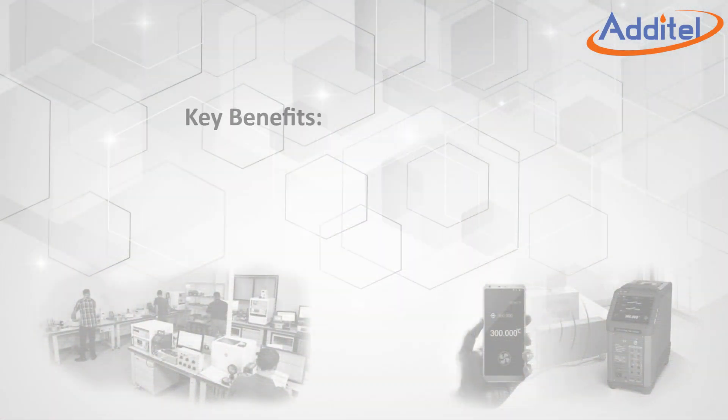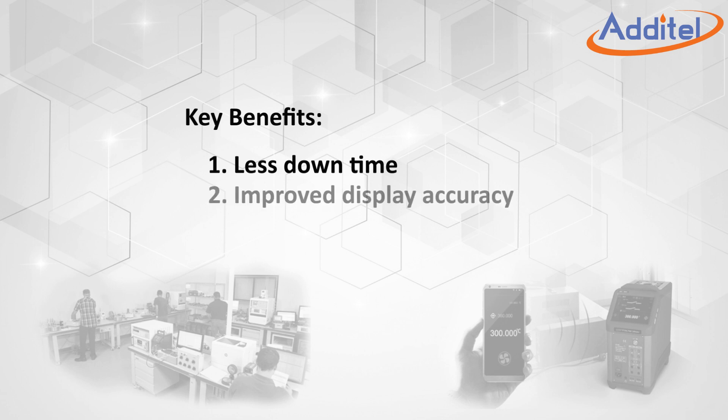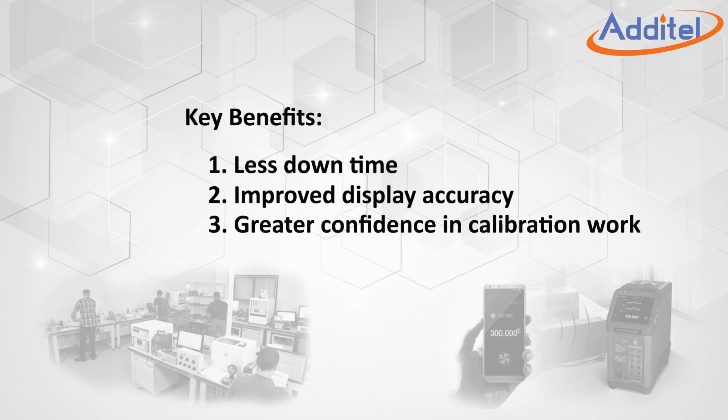The key benefits of Additel's new self-calibration feature include the following. There is no need to ship the unit out for routine calibration, which results in less downtime. Users can choose to lower uncertainties, as long-term stability and hysteresis contributions can be more tightly managed. Users also enjoy a much higher confidence in the accuracy of the dry well, knowing the unit can be calibrated just minutes before use.